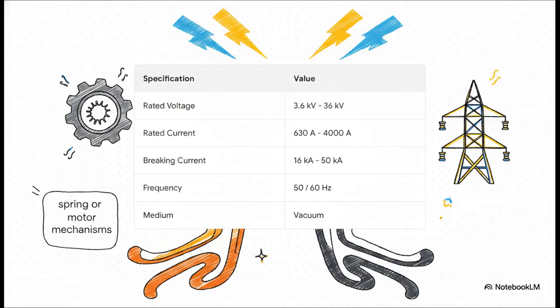Trying to wrap our heads around the massive scale of power this device handles is kind of crazy. A standard VCB operates at rated voltages anywhere from 3.6 kilovolts all the way up to 36 kilovolts, that's 36,000 volts. It can carry a rated current of up to 4,000 amps and handle a short-circuit breaking current up to 50 kiloamps. Operating at standard 50 or 60 hertz frequencies, driven by powerful spring or motor mechanisms, these specs highlight that the VCB isn't just a switch, it's a heavy-duty industrial powerhouse.